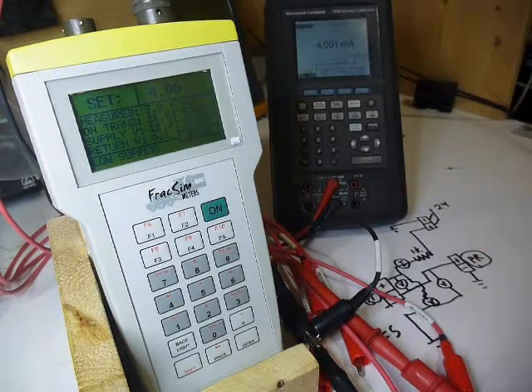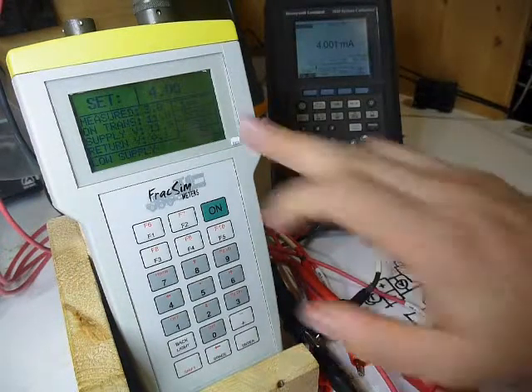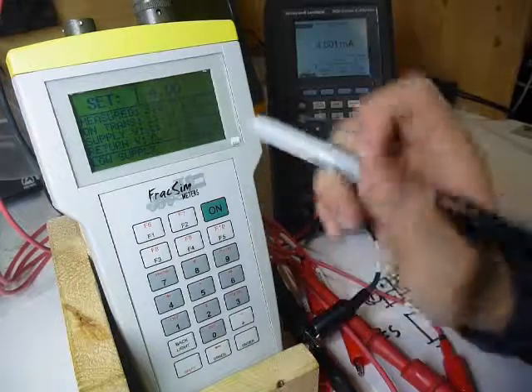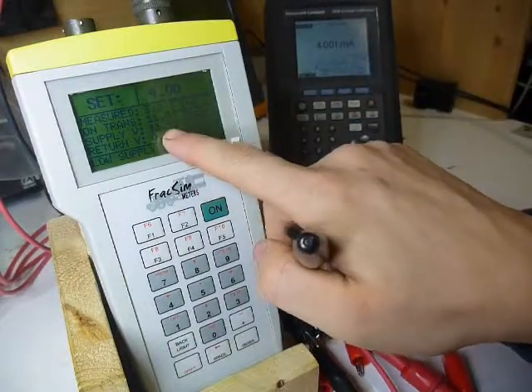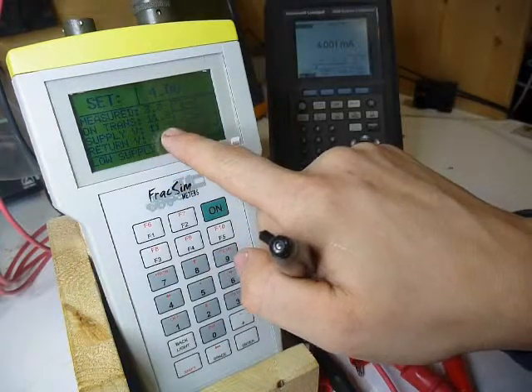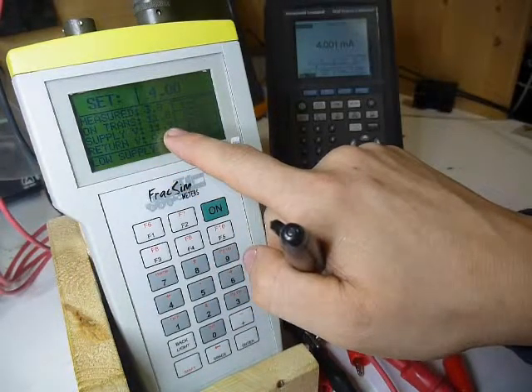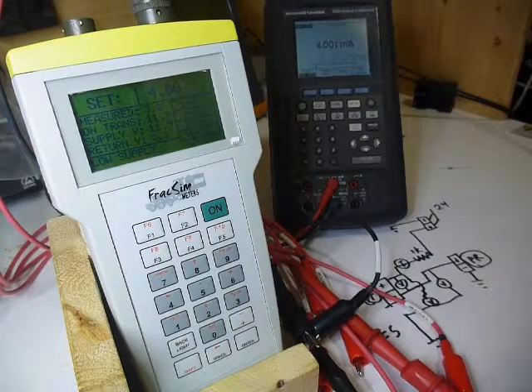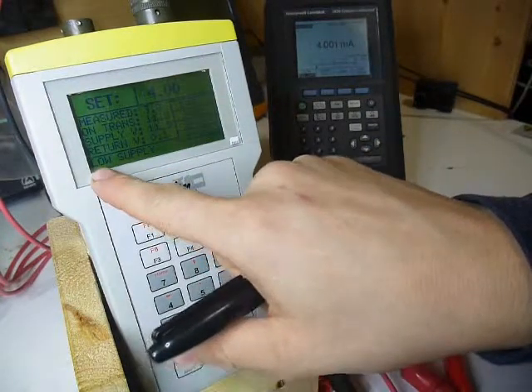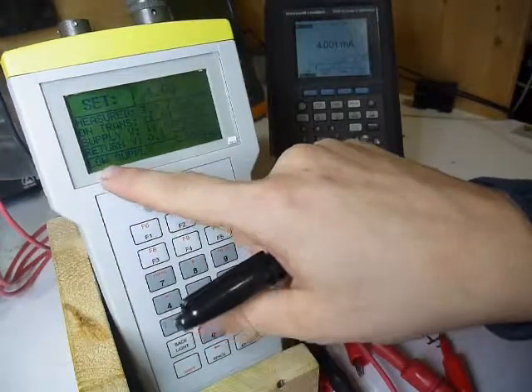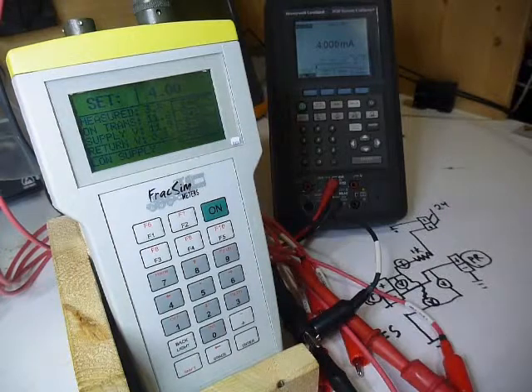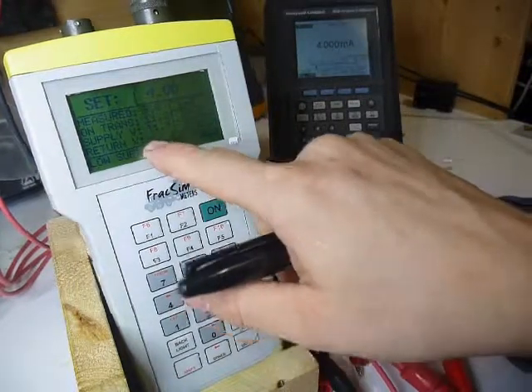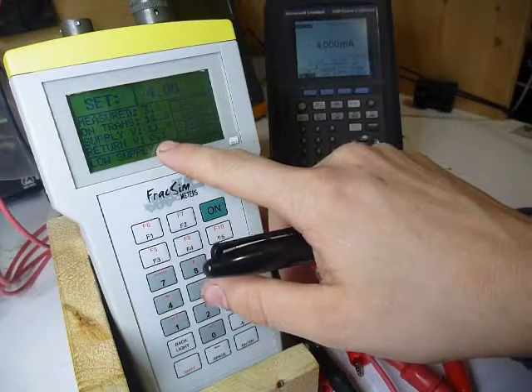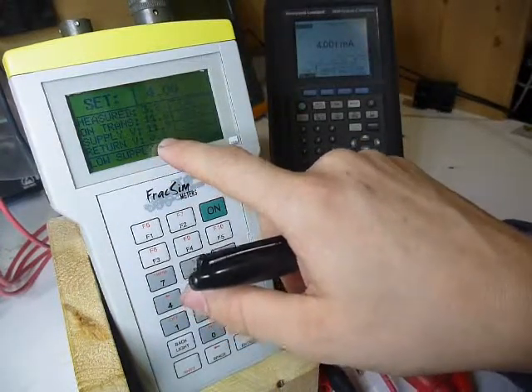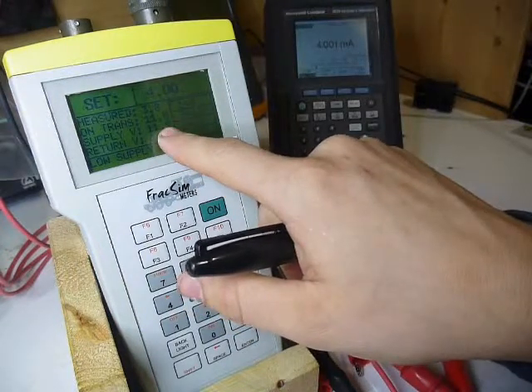So from this information, just like how we diagnosed the high resistance in the return signal, you can see here that we have a high resistance in the supply signal, and the reason you're seeing that is because our supply voltage, which should be at 24 volts, has been dropped down to 12 volts by the resistor value we're using. And you can see that instead of the error message before being return ohms high, now it's low supply. So again, more useful information, and you can tell there's nothing in the return side. Our return voltage drop is pretty much nothing again. So you know that the problem's not on that return side.